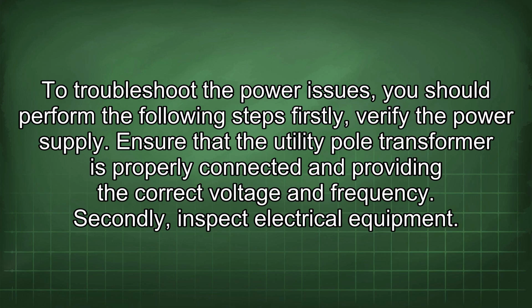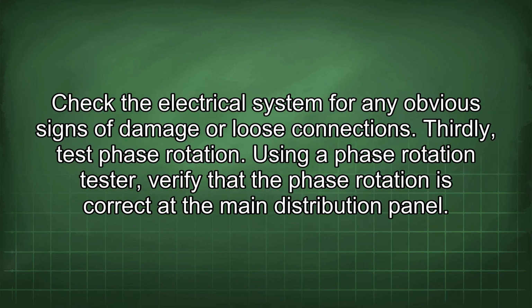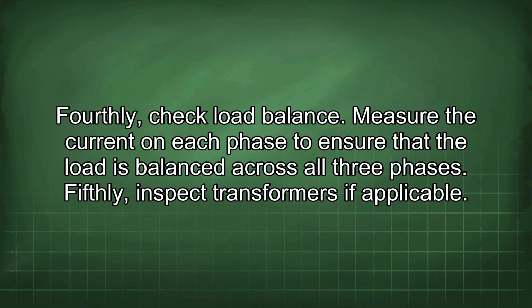Firstly, verify the power supply. Ensure that the utility pole transformer is properly connected and providing the correct voltage and frequency. Secondly, inspect electrical equipment. Check the electrical system for any obvious signs of damage or loose connections. Thirdly, test phase rotation. Using a phase rotation tester, verify that the phase rotation is correct at the main distribution panel. Fourthly, check load balance. Measure the current on each phase to ensure that the load is balanced across all three phases.